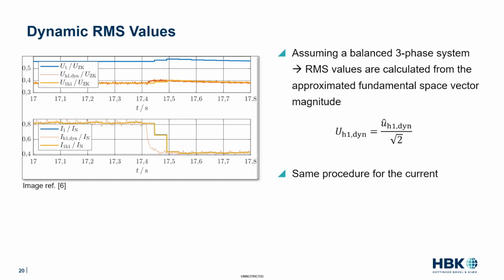Looking in detail at the voltages: the blue curve is the RMS value of the inverter output voltage including all harmonics. The yellow curve is the RMS value of the fundamental of the inverter output voltage, calculated with the conventional method based on the fundamental cycle. The red curve is the dynamic approximation. You can see the same for the currents.